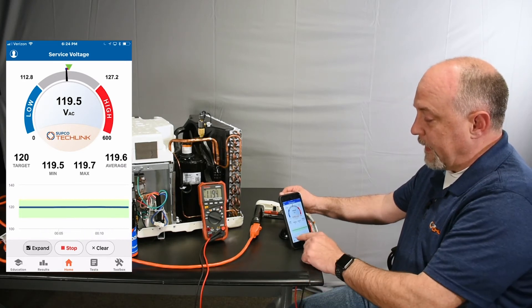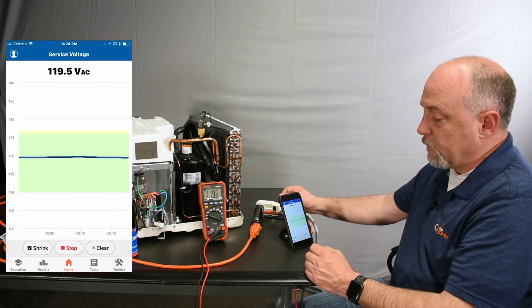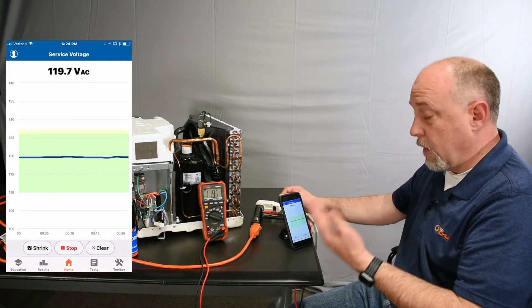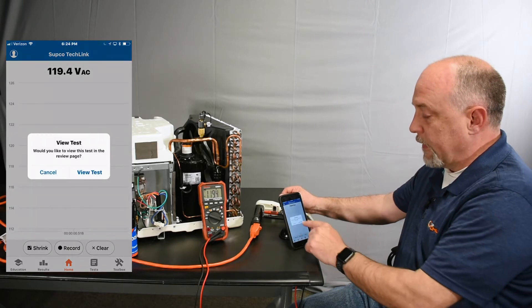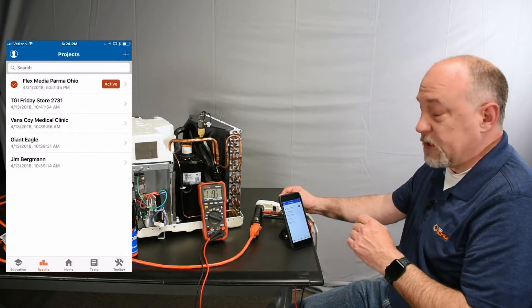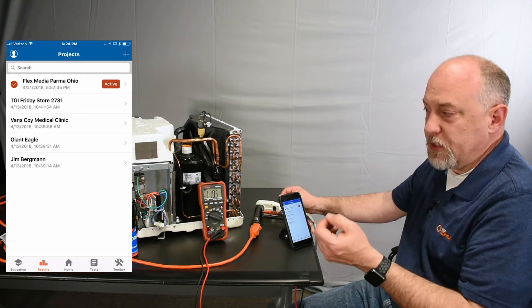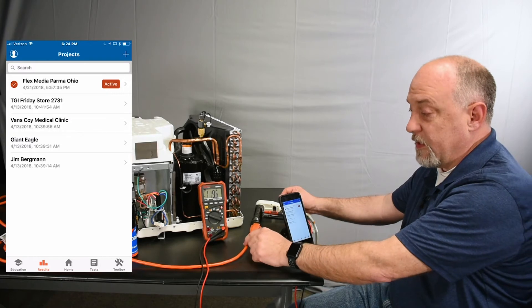If I expand this, you can see we're right in the center of what our service voltage should be. This is just a test we would do with the system in off mode. I'll hit stop and record that. The difference between service voltage and utilization test is service voltage is what we have delivered—the electrical pressure coming out of the end of this cord.